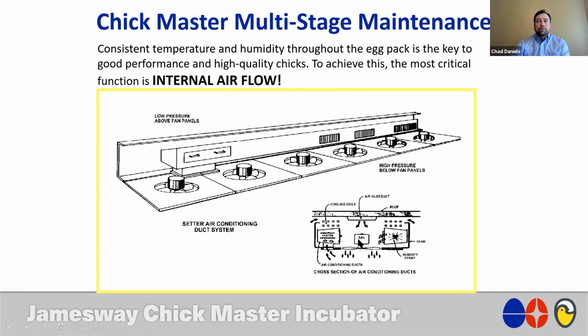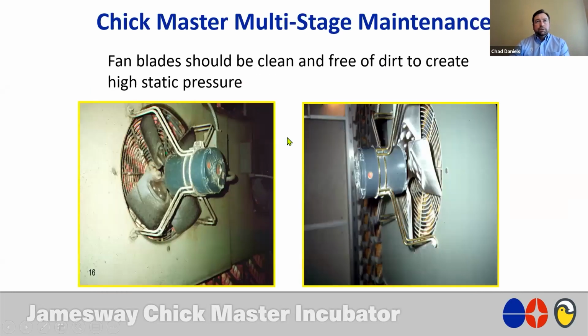So if the fan is in really good operating condition, the volume of air that it pulls in is going to be higher than if we have an issue with this fan. And so that's what's important to keep in mind when you think about how critical it is to make sure that these fans are in good shape. We look at some examples of that. The picture here on the left, you can see a lot of dirt and debris build up on this fan blade.